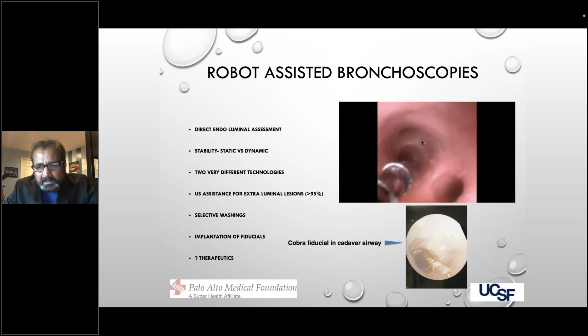So the Auris Monarch platform is largely modeled on the Veran platform. It uses an ipsilateral field generator, where the field generator is on the side of the patient. It uses a tip tracking mechanism. There is no respiratory gating. The outer diameter of the distal catheter is about 4.5 millimeters. It has an irrigation system where you can pump in air or saline or water to distend the airway as you move forward, which may or may not be a good thing.